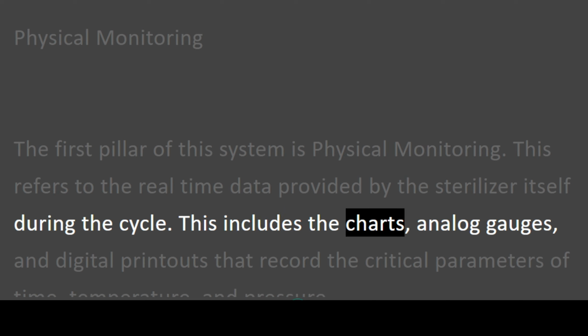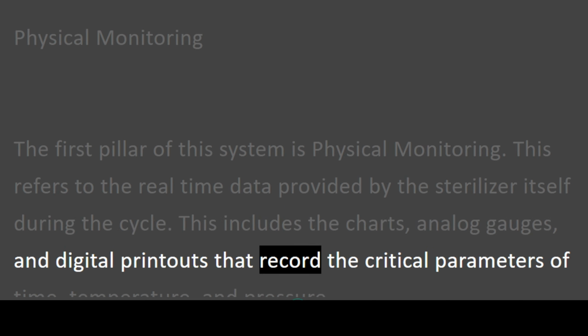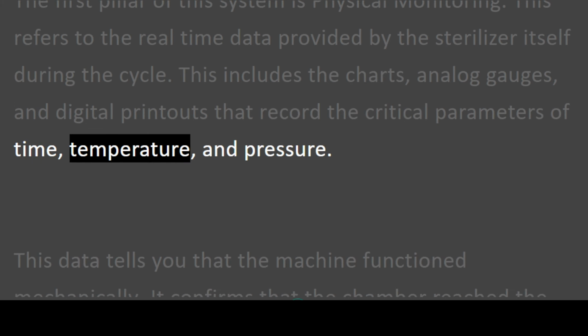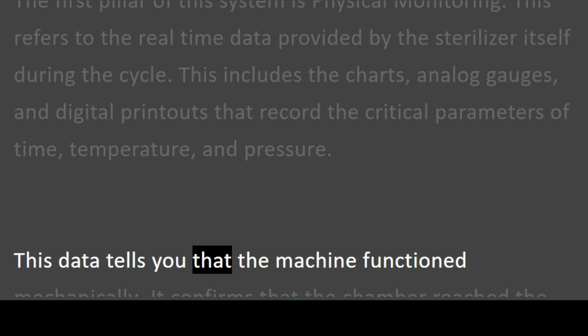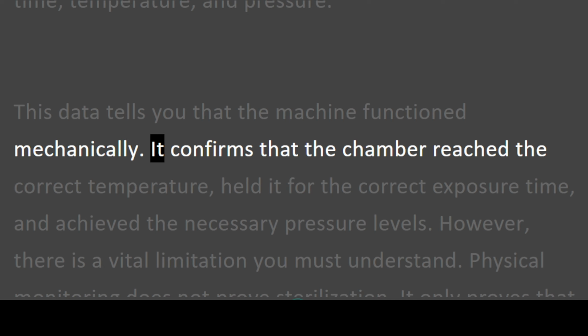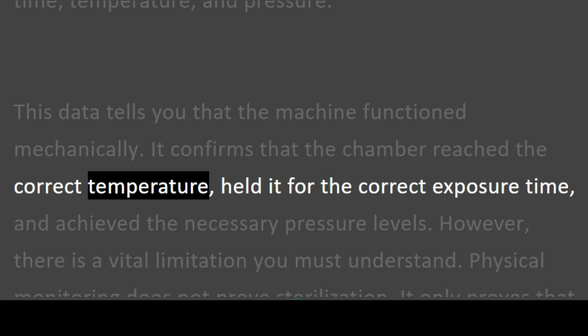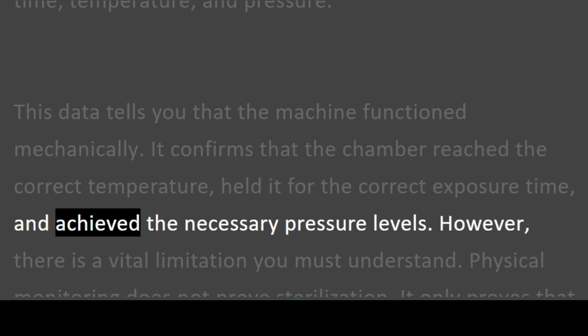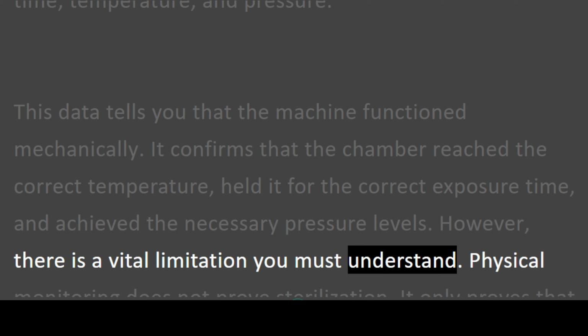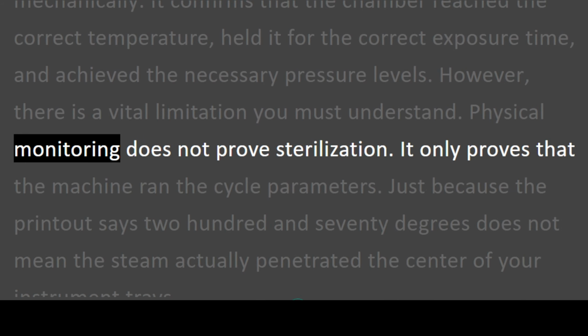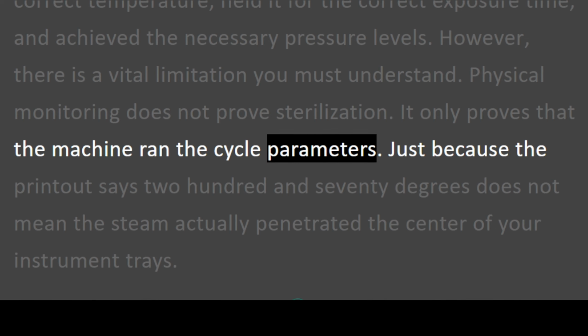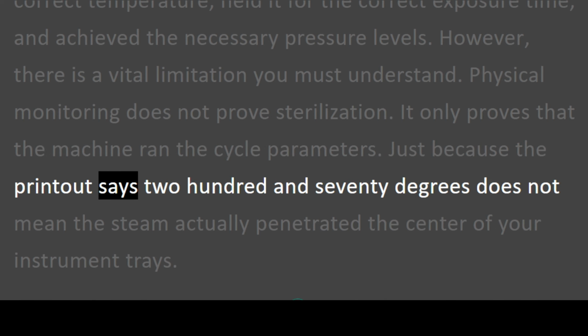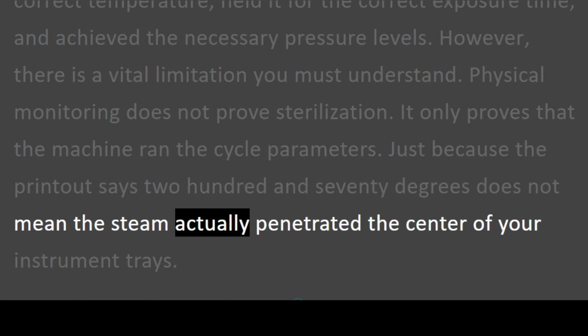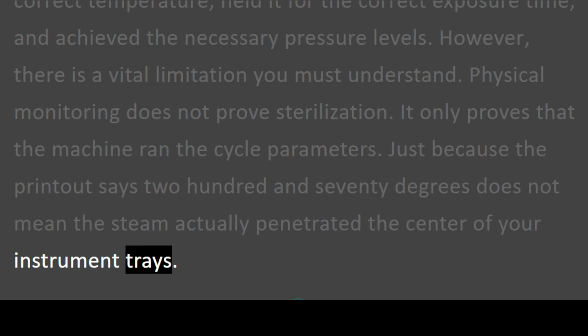This includes the charts, analog gauges, and digital printouts that record the critical parameters of time, temperature, and pressure. This data tells you that the machine functioned mechanically. It confirms that the chamber reached the correct temperature, held it for the correct exposure time, and achieved the necessary pressure levels. However, there is a vital limitation you must understand. Physical monitoring does not prove sterilization. It only proves that the machine ran the cycle parameters. Just because the printout says 270 degrees does not mean the steam actually penetrated the center of your instrument trays.